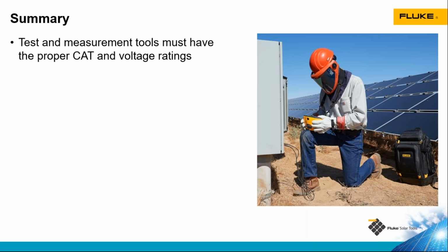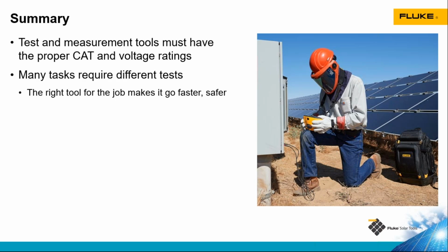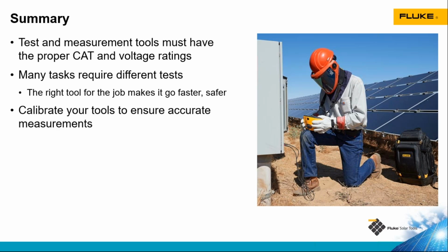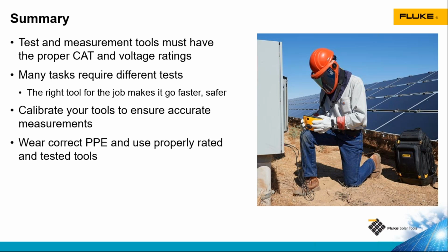So to wrap things up, there are lots of test and measurement tools in the solar industry. They need to have the proper category and voltage rating for the environment and the voltage levels at which you will be doing your testing. We've got many different tests to do. We have tools for each test. Selecting the proper tool is going to give you better results, faster and safer, which is really important. We need to calibrate our tools to make sure that they are operating properly and giving us good test results.